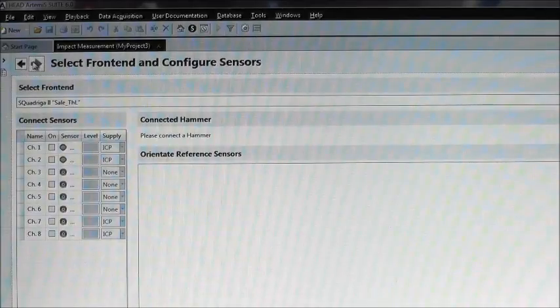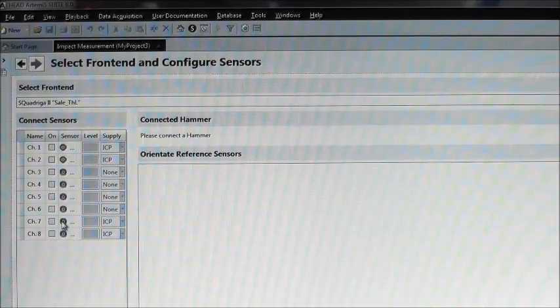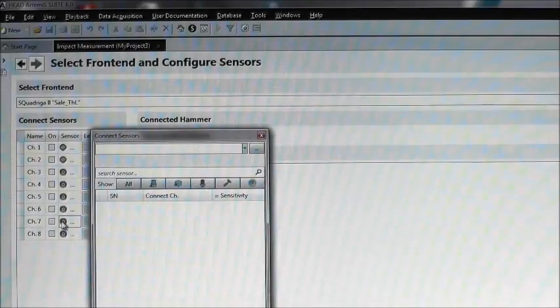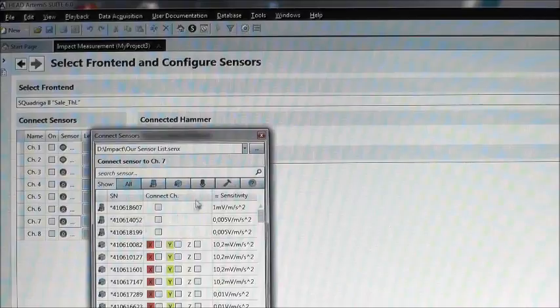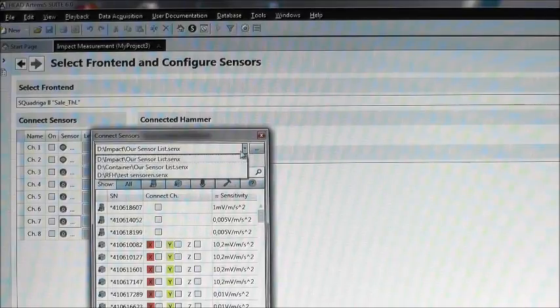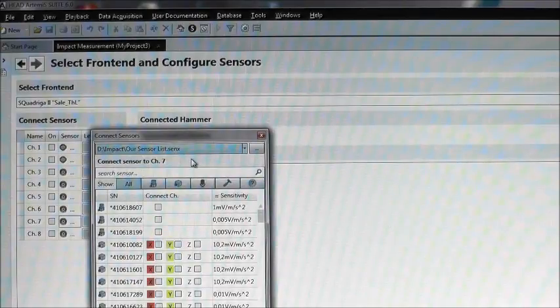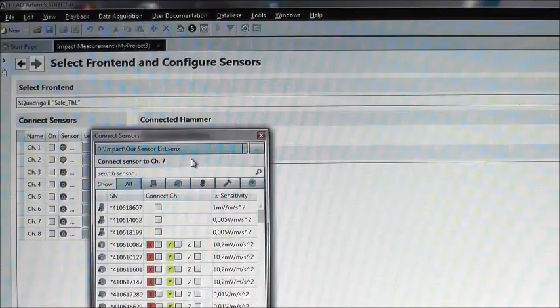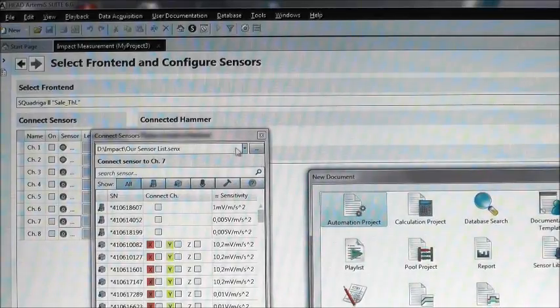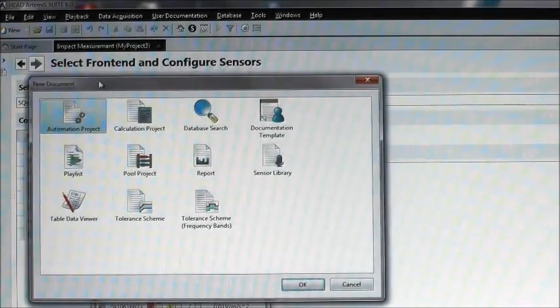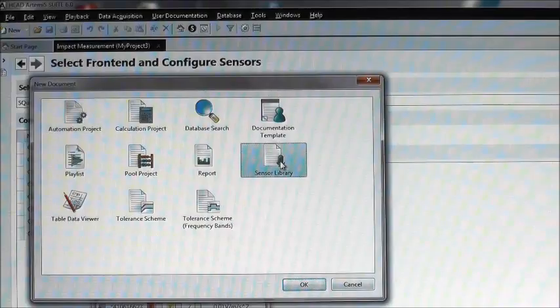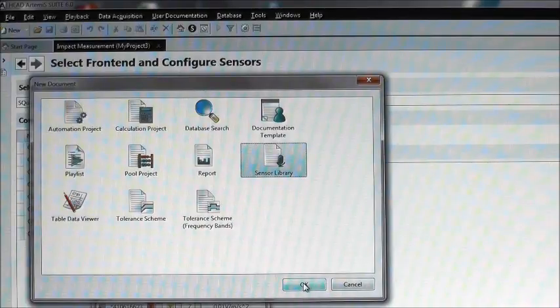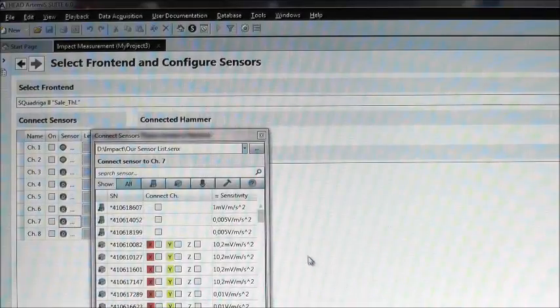We will select our front-end and sensors in the next step. The SQuadriga 2 has already been found and selected. We will use channels 7 and 8. The impact hammer is connected to channel 7. We will need a sensor library containing the sensor definitions. We can select a prepared library up here. If there is no library, we could do this right now. Go to New and choose Sensor Library. Creating new sensor library is easy. We will skip it for now. I will use my existing library.